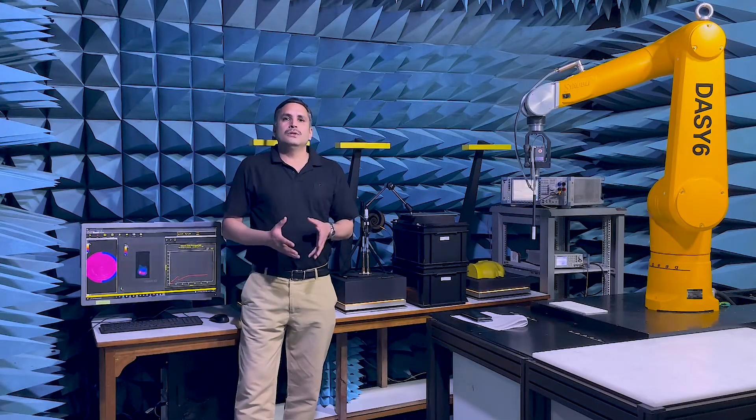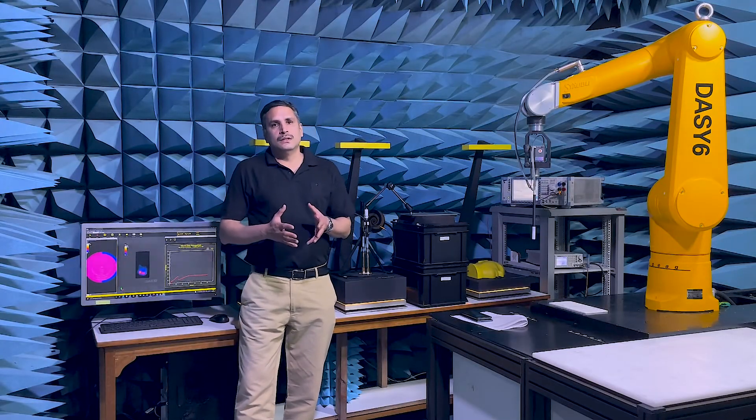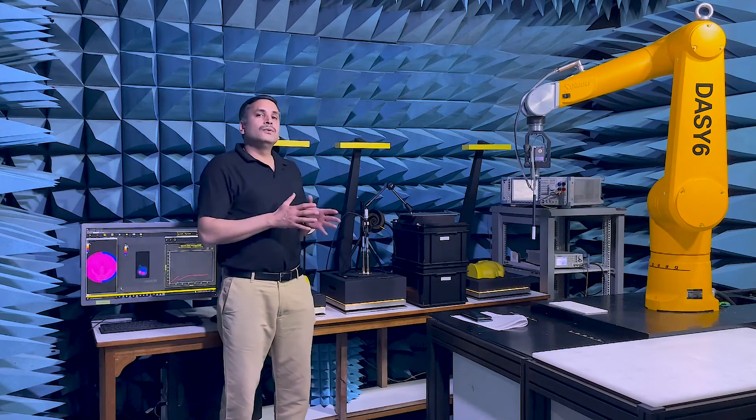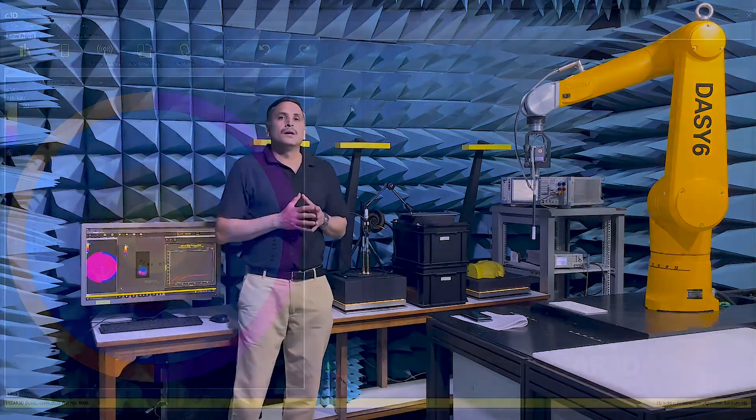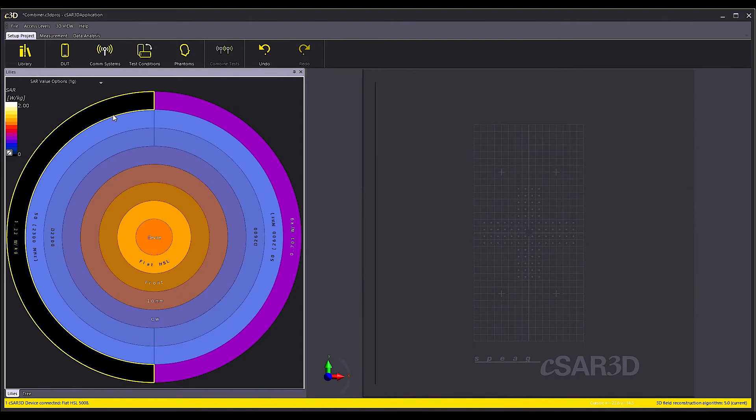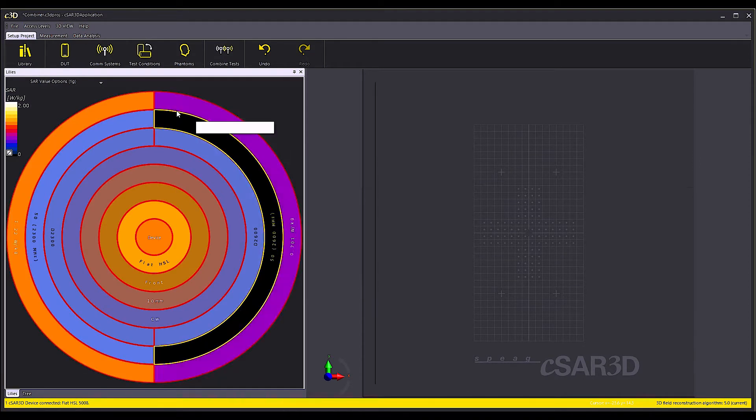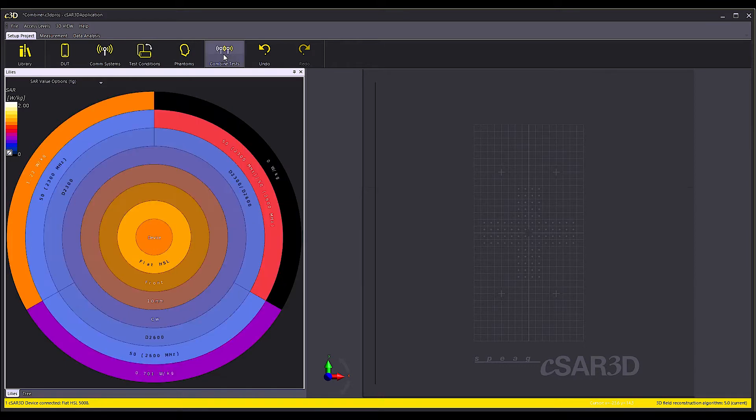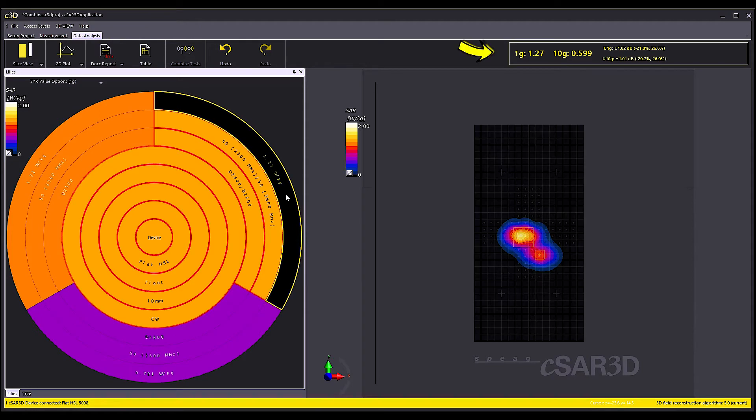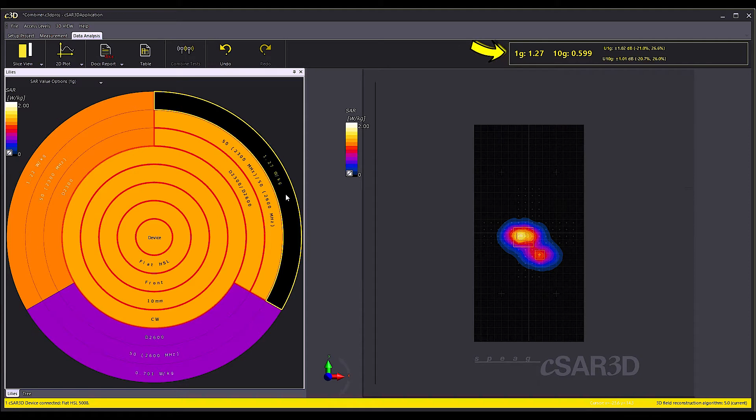The two dipoles thus transmit with a 50% duty cycle. I have established the target value before by measuring each antenna individually with 50% power and combined the two measurements using the combiner. The combined values are 1.27 Watt per kg for 1 gram and 0.599 Watt per kg for 10 gram that is now the target value for this test.